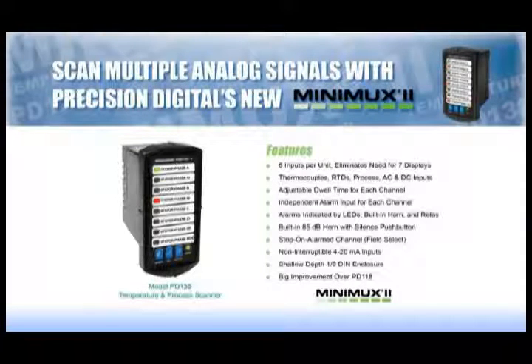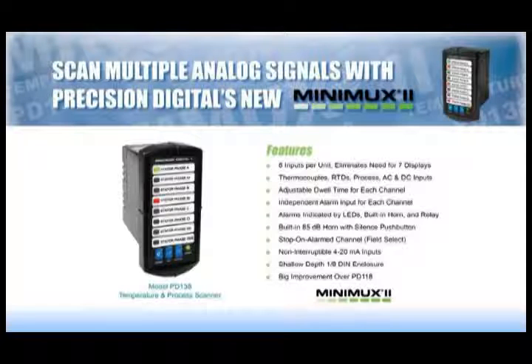One of the key features of the PD-138 is that it eliminates the need for seven extra displays. All you need is one Minimux and one meter, and you can automatically scan and check for alarm on up to eight inputs. The standard dwell time for each channel is four seconds, but each channel is fully adjustable between a half and 30 seconds. You can also program a channel to be skipped, and you can also stop the scan by pressing the stop-go button.